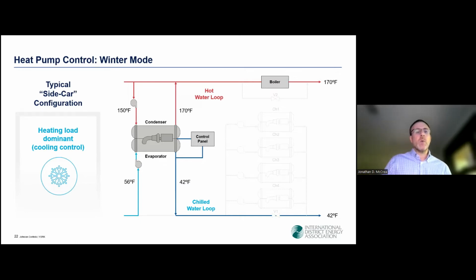And it's important to note that in this setup, our chilled water load is our heat source. And it's also the limiting factor in how much hot water we can produce with the heat pump. And we'll talk about this more in our second session coming up. But if you had a sufficient additional heat source and enough heat pump capacity, we could potentially handle all of the heating load and eliminate the need to run boilers at all.